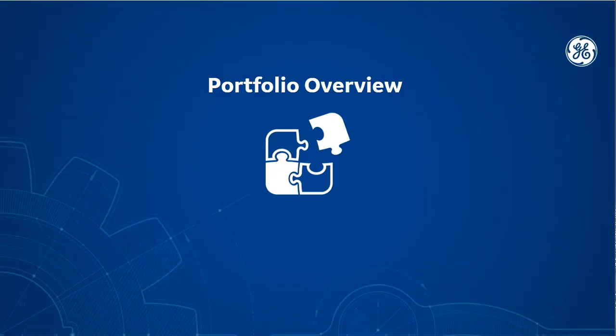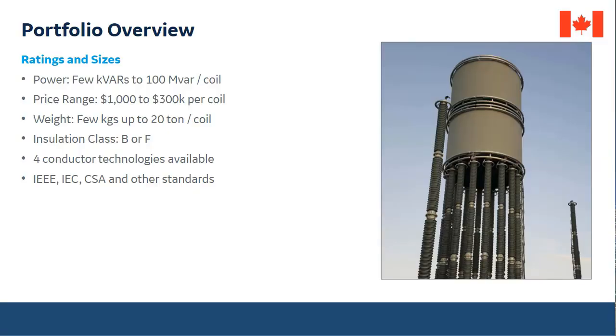So let us talk about a few characteristics of the reactor really quick here. Reactors can range from a very small power rating to a very large power rating, like a few kVars to 100 or maybe more MVars per coil. And we could have a phase with several coils connected in series, for example. They can be very small in terms of price, like $1,000, but they can be more than $300,000 or $400,000 per coil. They can weigh a few kilograms or pounds up to 20 or 40,000 pounds per coil. There are different types of construction materials. I'm mentioning here the insulation class: B, F, or H.